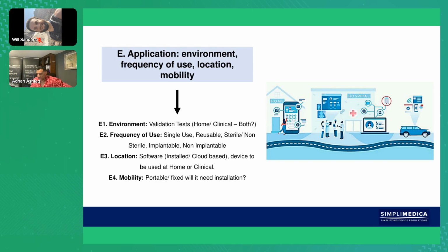Now, bearing in mind, we also have to have a look at our quality management system. So in our QMS, if we didn't have a procedure for installation, we have a problem. We need to make sure that we have an SOP or a procedure in our QMS that covers installation. Because maybe we had made a non-application in our quality manual against ISO 13485 and said that the device that we are manufacturing is never going to be installed.